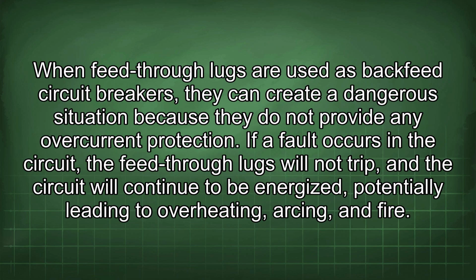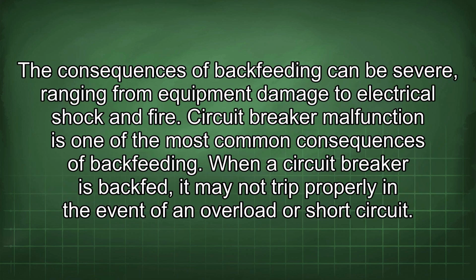When feed-through lugs are used as backfeed circuit breakers, they can create a dangerous situation because they do not provide any overcurrent protection. If a fault occurs in the circuit, the feed-through lugs will not trip, and the circuit will continue to be energized, potentially leading to overheating, arcing, and fire. The consequences of backfeeding can be severe, ranging from equipment damage to electrical shock and fire.